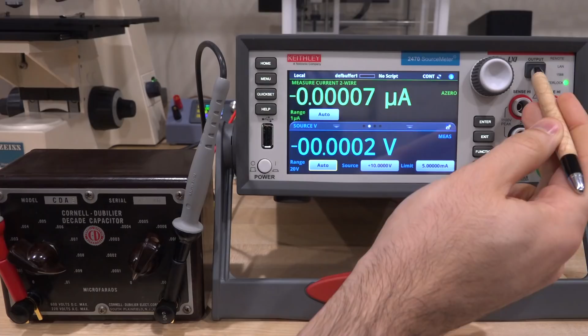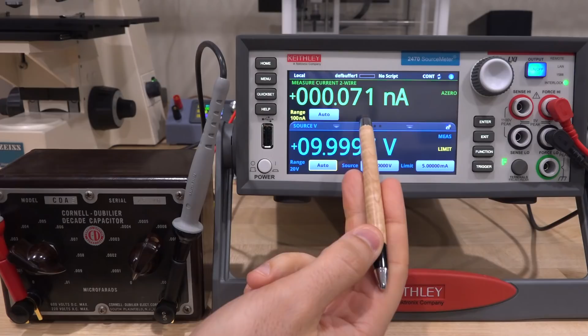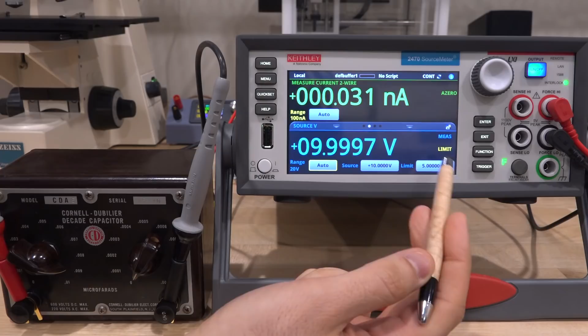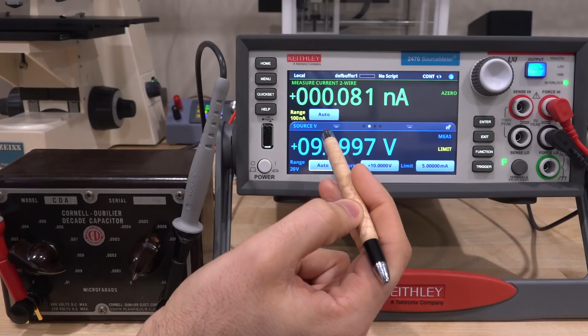So the capacitor is now connected to the SMU, and I have the SMU set to 10 volts. Let's enable the output and see what happens. There it is—under this condition we have 10 volts. We're essentially in the noise of this instrument, and there's some algorithms with the auto ranging that sometimes cause this limit to show up. I've spoken with Keithley about this—I think they can optimize it a little better, depending on whether it's auto ranging or not. Right now we don't really see much leakage because the voltage is so small.